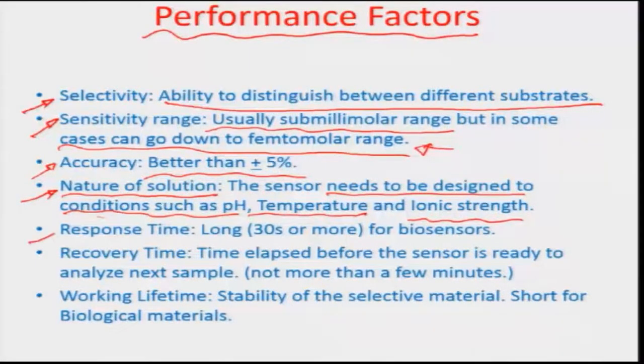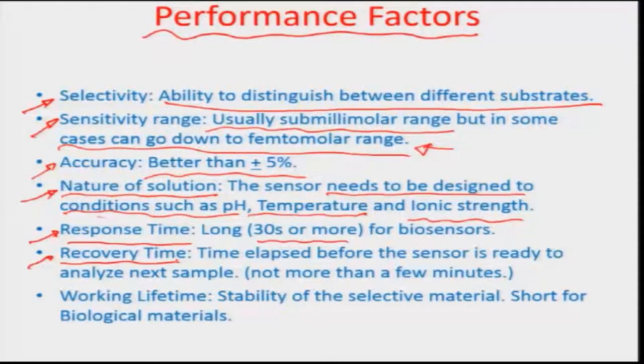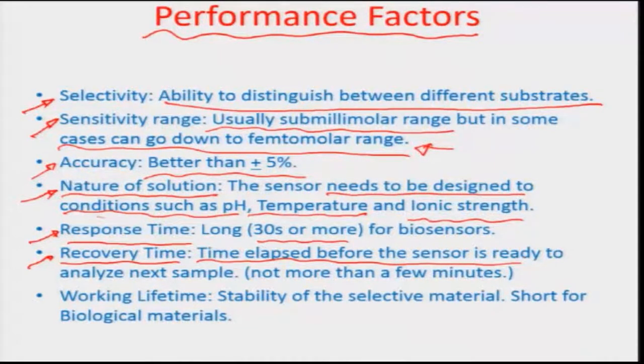The sensor also takes care of issues like the temperature range at which performance does not change, or what the ionic strength will be. Response time is another important performance factor — for gas sensing and biosensing applications, smaller is better, but with modern technology about 30 seconds or more of sensing time is considered quite reasonable. There is also a recovery aspect: once the sensor surface has sensed something, it should be able to return to the baseline signal. The time elapsed before the sensor is ready to analyze the next sample should typically not be more than a few minutes.